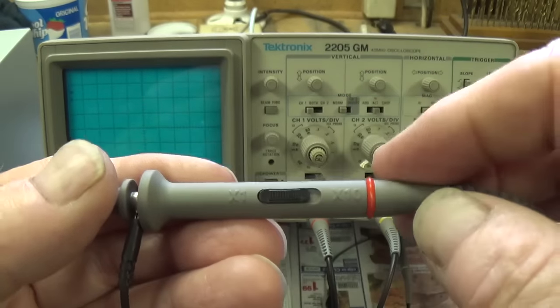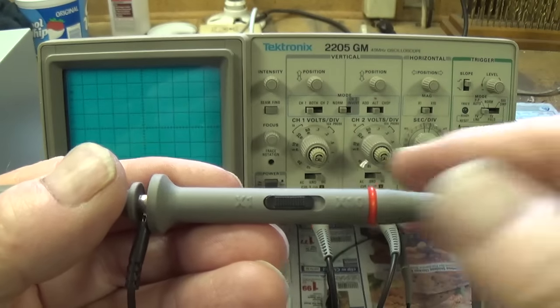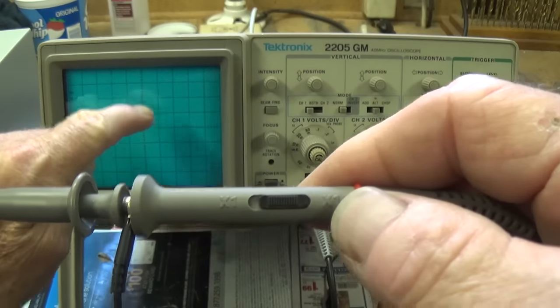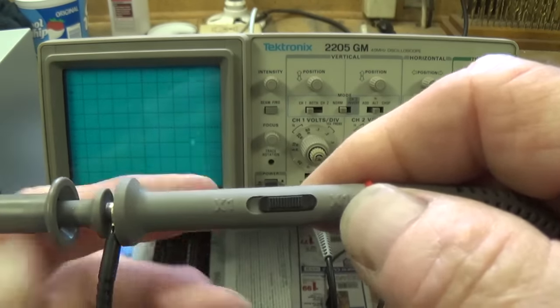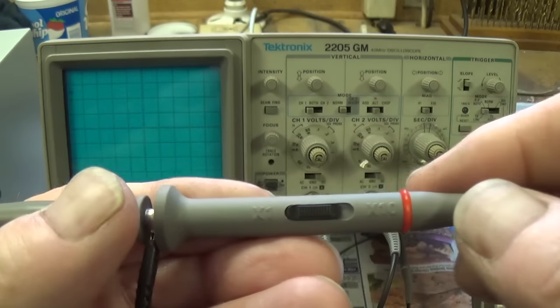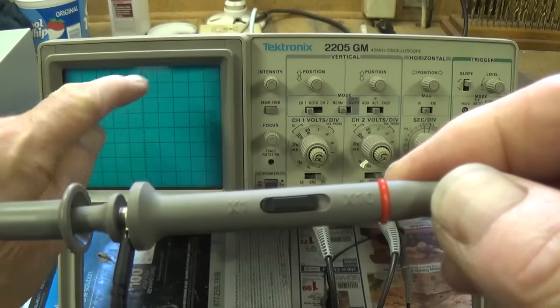So this gives you great flexibility as far as the voltage readings that you connect to. One thing you have to remember though is if you go to x10, remember that the image on the screen is 1 tenth as tall as it should be. The x1, you will get the valid height.